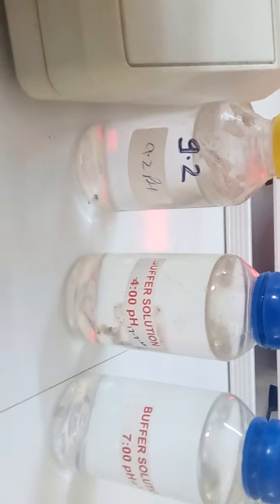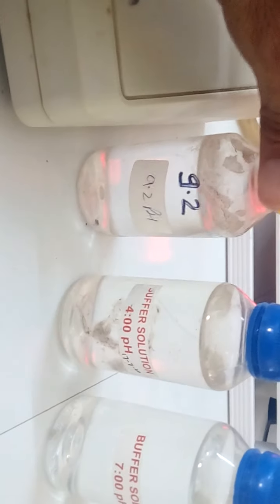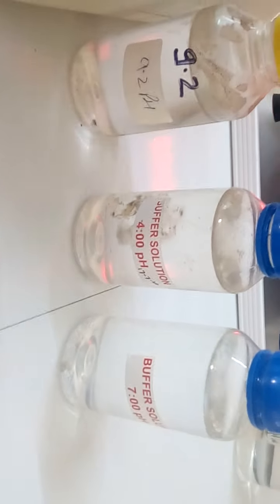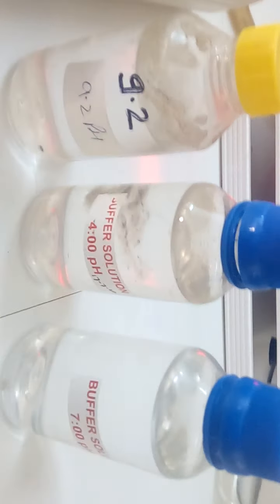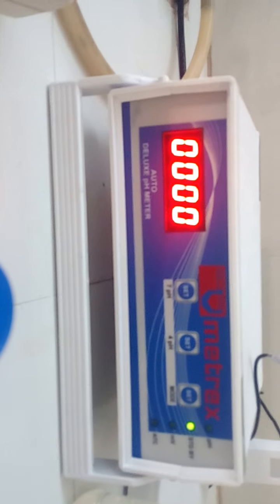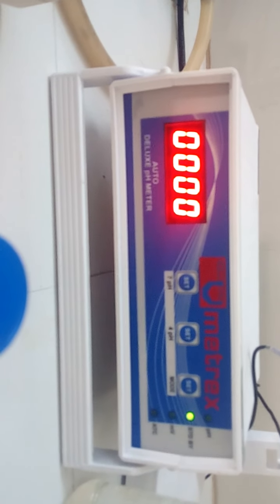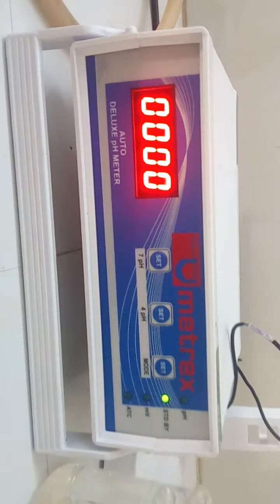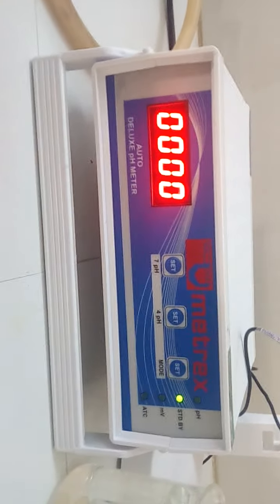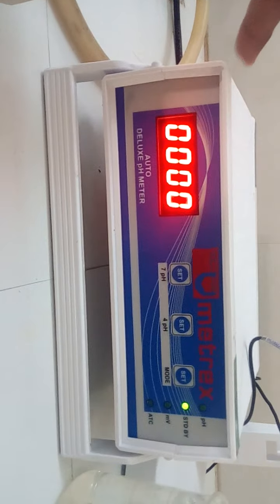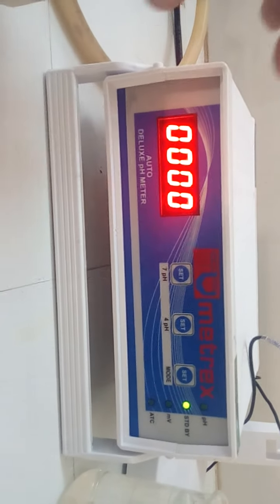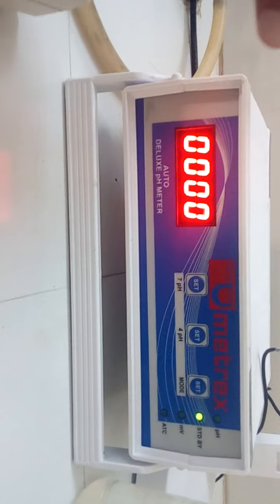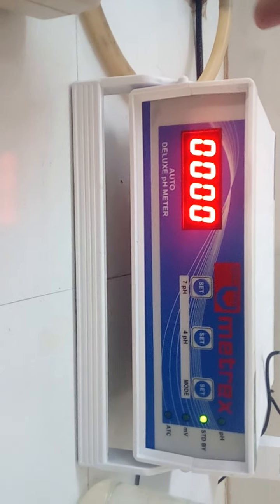These solutions are buffer solutions: the 9.2 pH buffer solution, the 4 pH buffer solution and the 7 pH buffer solution, which are used for calibration of the pH meter. After measuring any unknown solution's pH, we can calibrate the pH meter. So we get started with the calibration process. At this time the pH meter is on standby position. Standby position means current is not flowing, and no measurement is shown on the display.